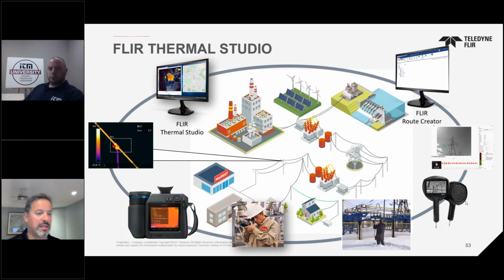This was a laboratory test done by a third party, imagining a 1 cubic yard area of space, where they looked through the lens and could pick up particles down to 2 ppm. That's very small for gas leaks, but these are specialized cameras. This is thermal imaging with special filtering, looking for a specific type of leak.